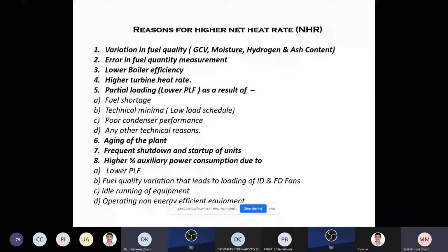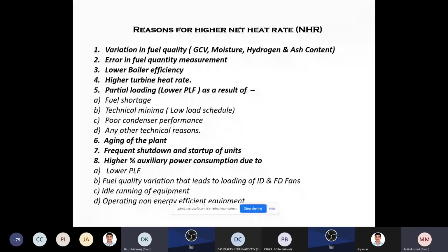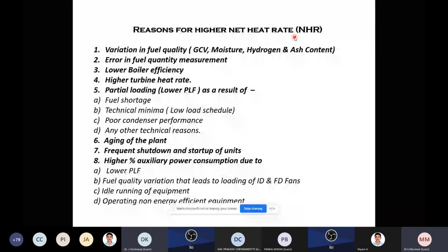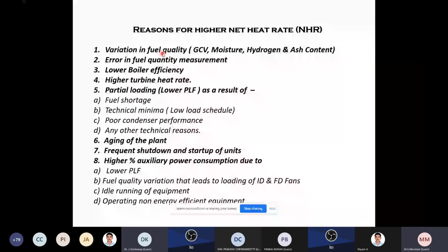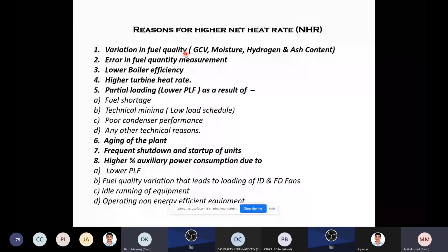Now, there is some explanation you will have to give when there is a net heat rate. It does not mean that the net heat rate always depends on the fuel quality or something else, so I have tried to establish that there are many variations. Suppose the gross heat rate, net heat rate variations will be there, or it will show high if there is a variation in the fuel quality. Suppose in your first lot the GCV is very good, and in the second lot the GCV is not good. So automatically your heat rate will change.